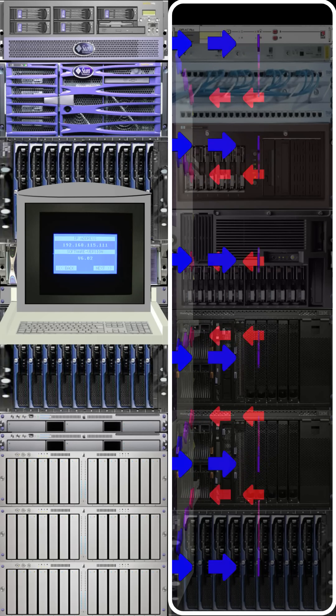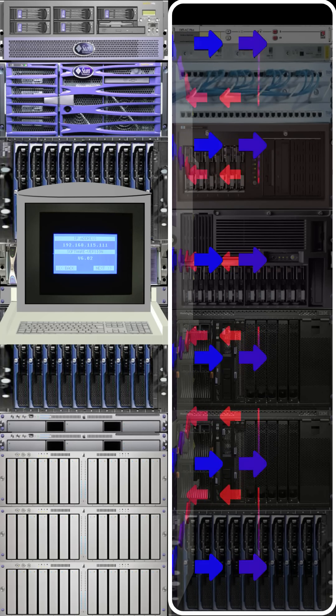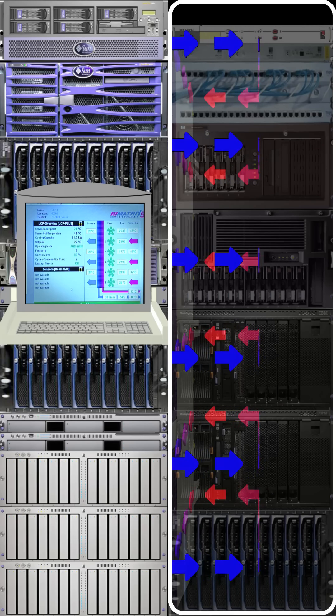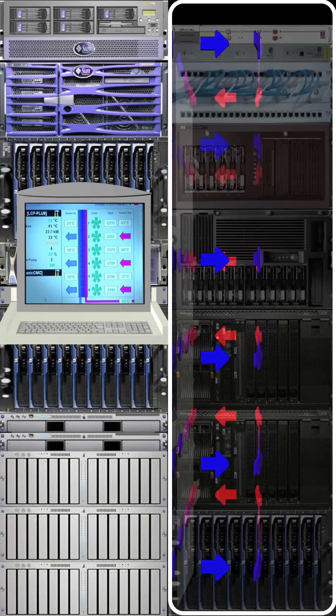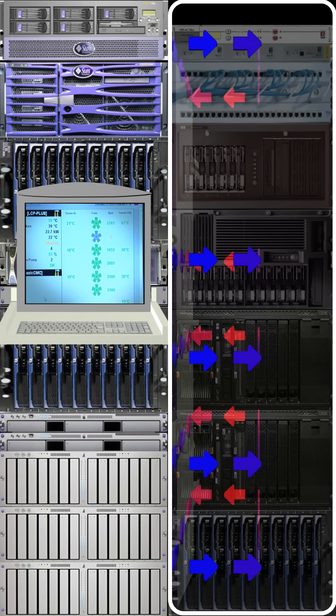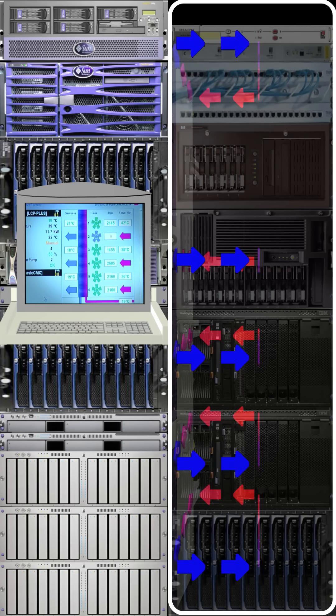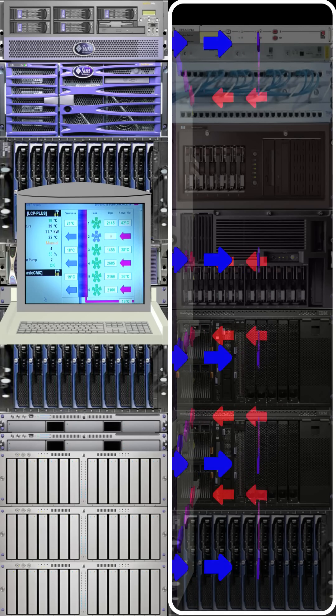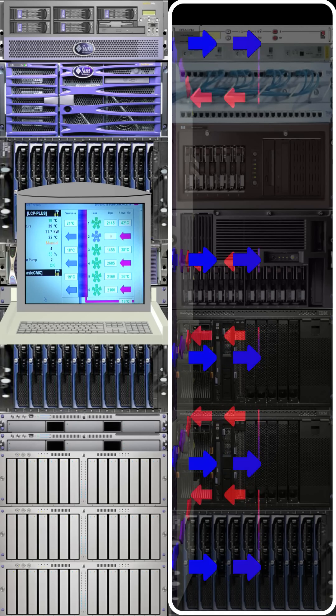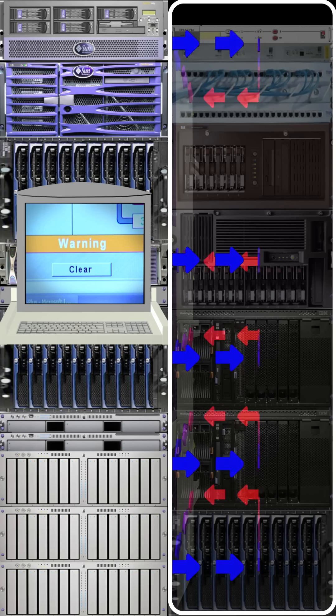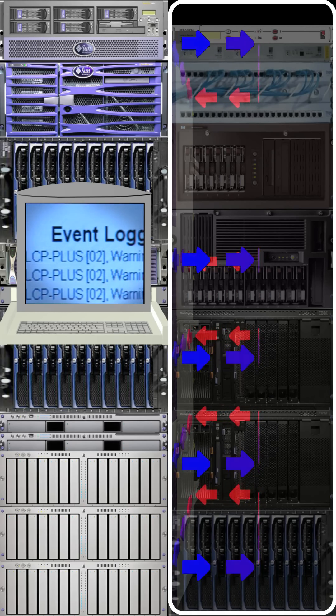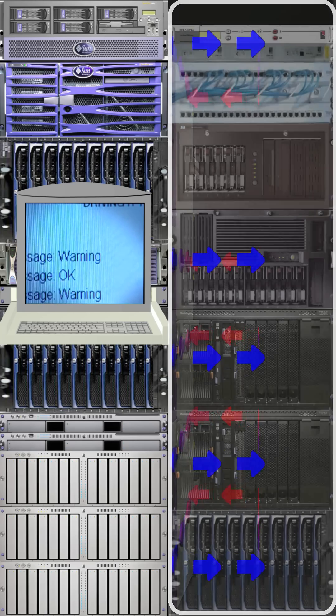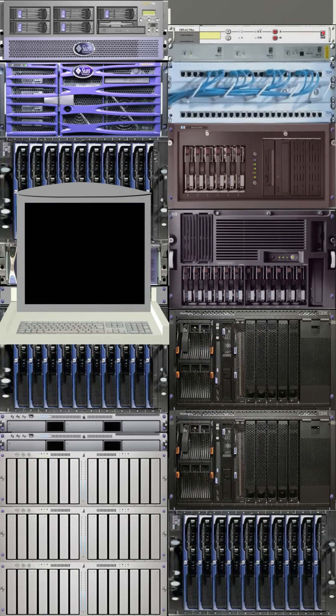The LCP Plus can be directly connected to your network and via a web browser or an NMS, you can see a graphical status display. A mimic diagram shows the key elements of the LCP Plus and visually displays any fault. SNMP traps can be sent to network management software to alert remote users of any issues. Alarm logs are stored and are easily accessible via the web browser.